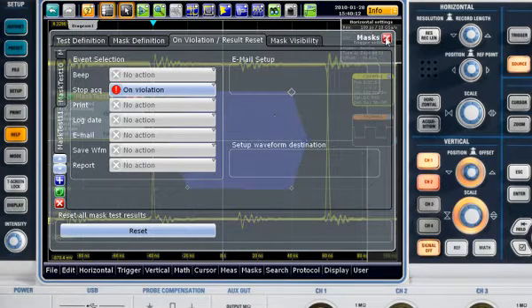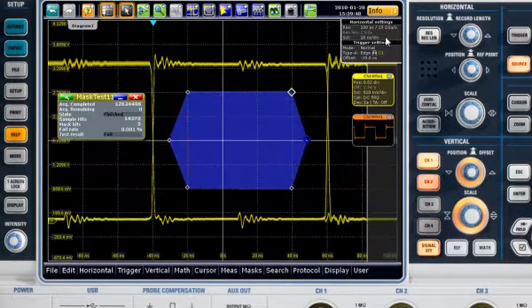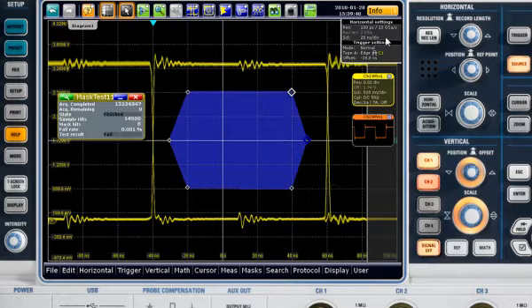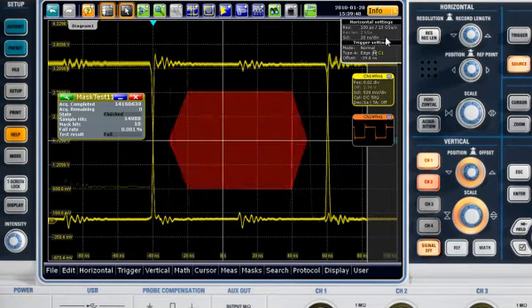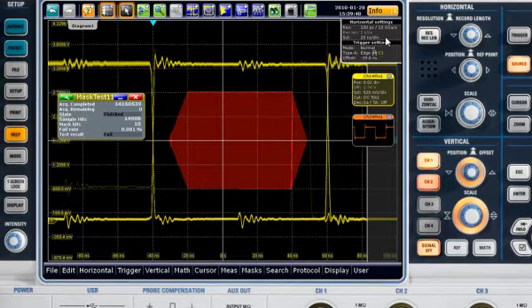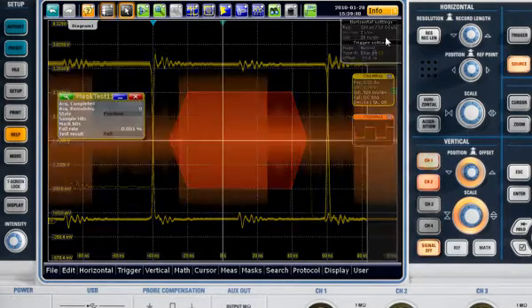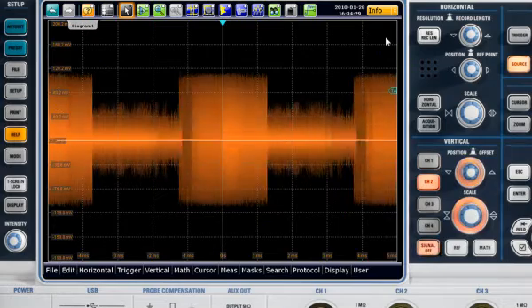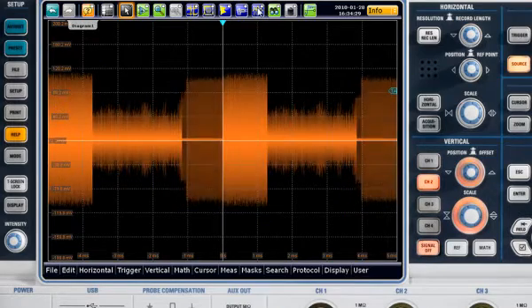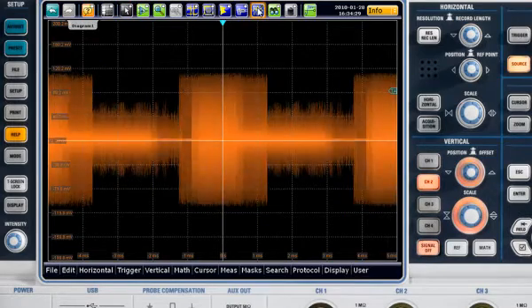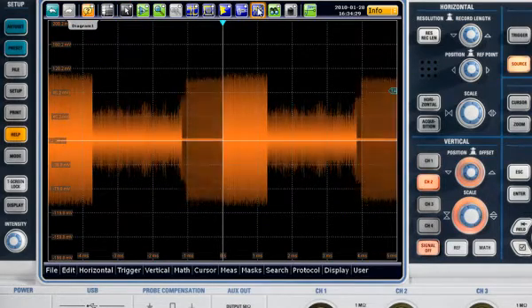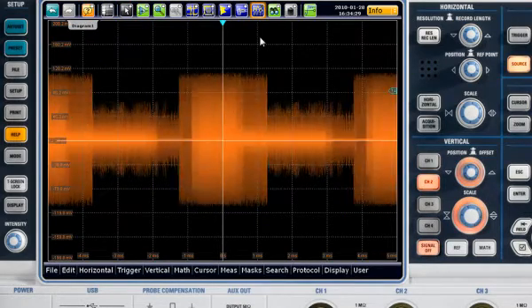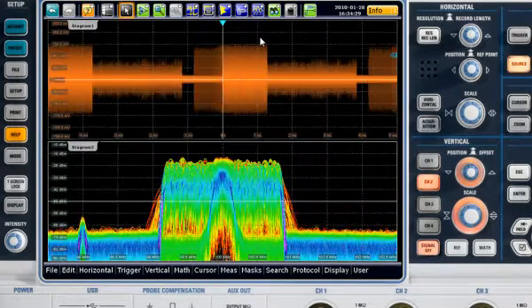In the event that a waveform fails a mask test, you can stop the recording and use the history function to go back to previous waveforms. The FFT icon in the toolbar gives fast access to the frequency domain.